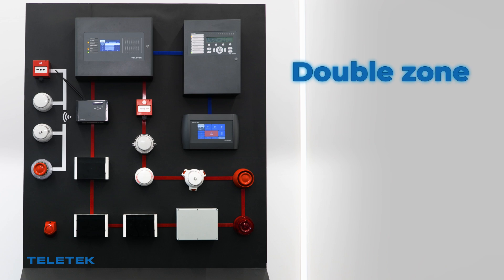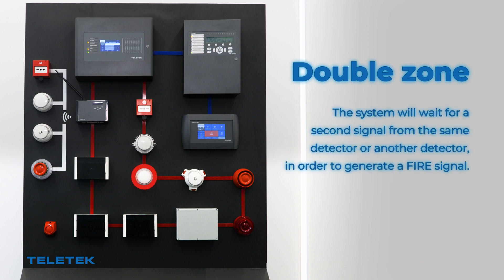Double Zone mode: any detector activation within the system generates a pre-alarm to the respective zone. However, the system will wait for a second signal from the same detector or another detector in order to trigger a fire alarm signal.